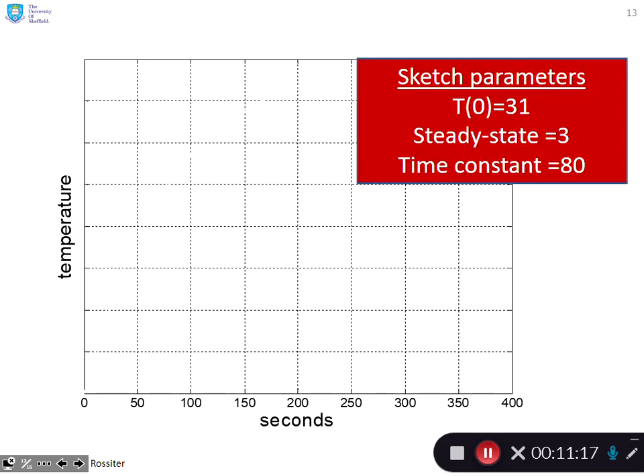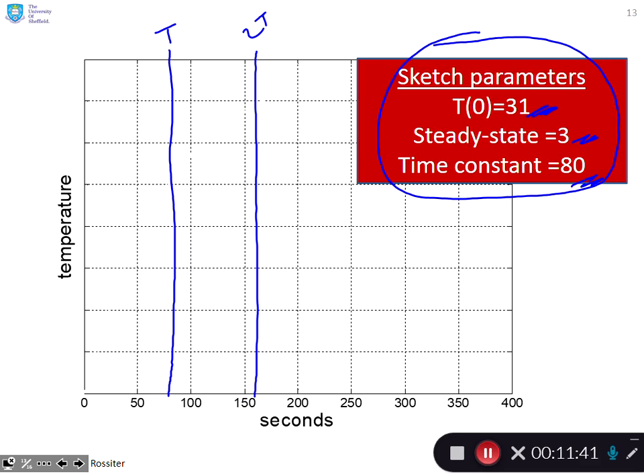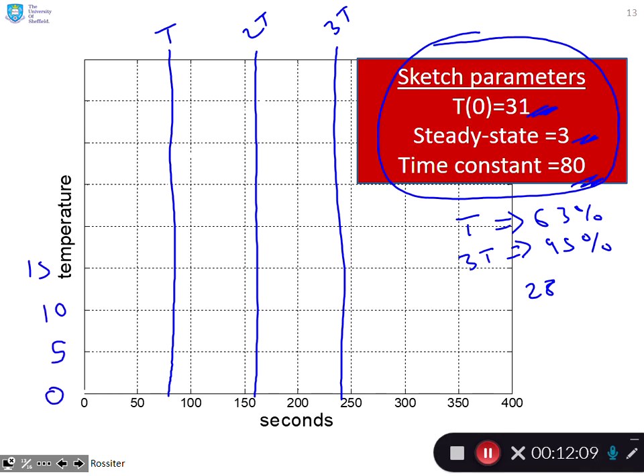The first thing I've done is summarized my key information: start point 31, end point 3 (that's 31 minus 28), and time constant of 80. I put the time constants on. I know that after T you get 63% movement, after 3T you get 95% movement, and the total movement is 28.